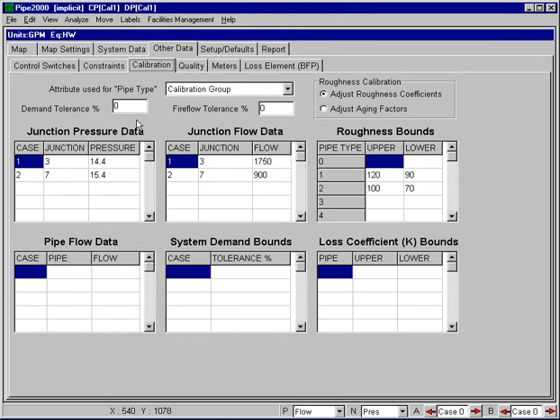As an example, if the user were to specify a total system demand of 1 million gallons per day in the original data and then specify a tolerance in this cell here, say, of 5%, then the calibration algorithm would allow the total system demand to vary between 0.95 mgd and 1.05 mgd during the calibration process. And so we'll try to use that tolerance there to try to improve on our final calibration.